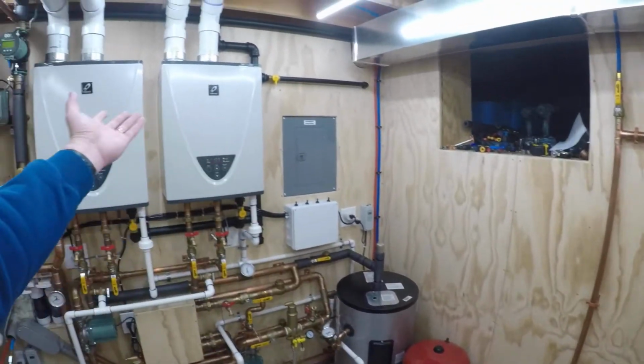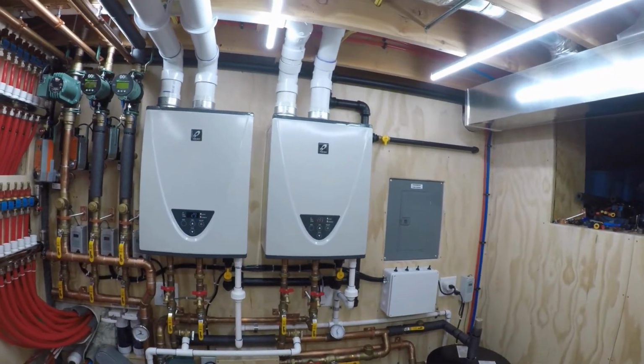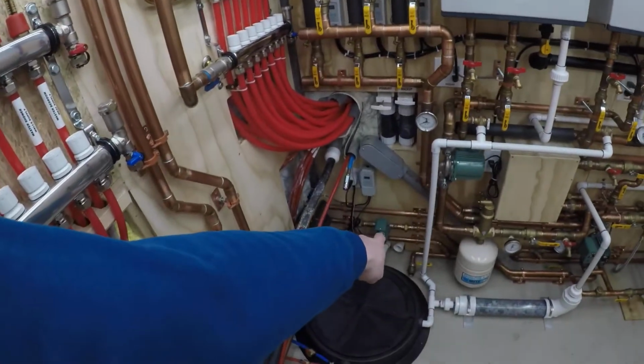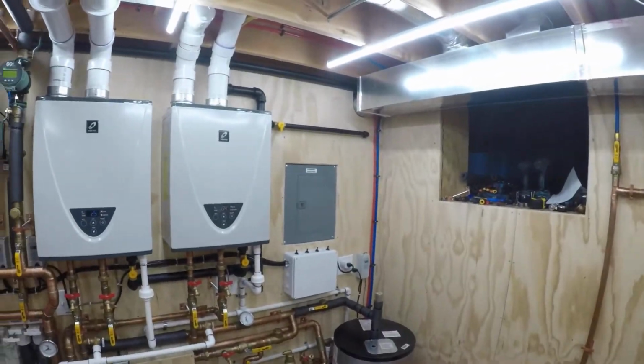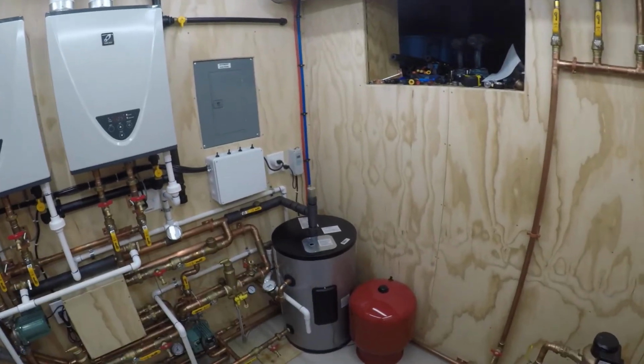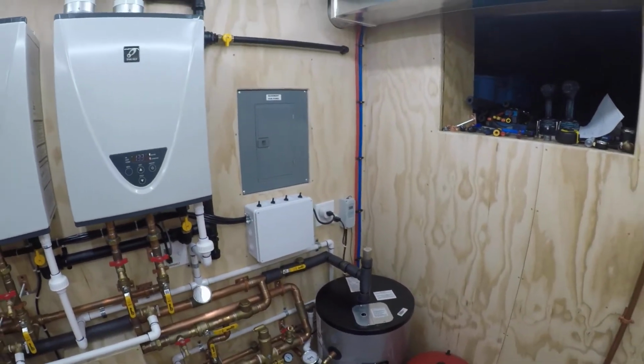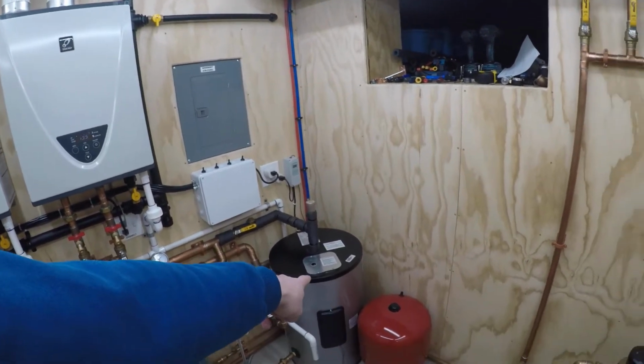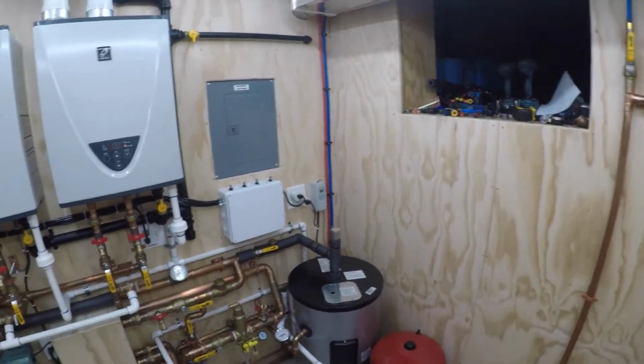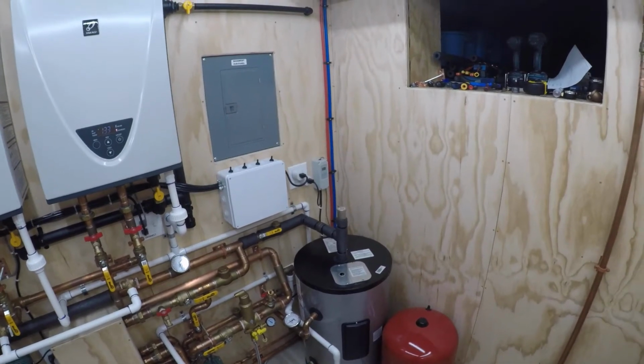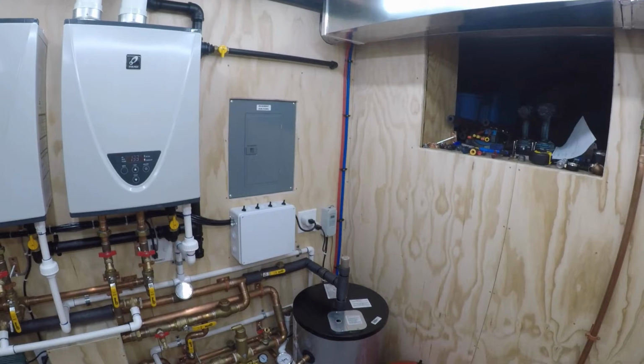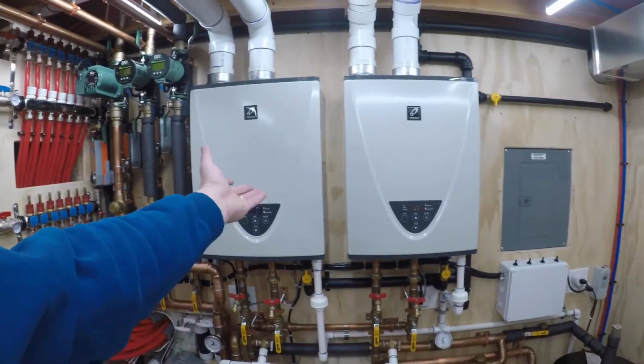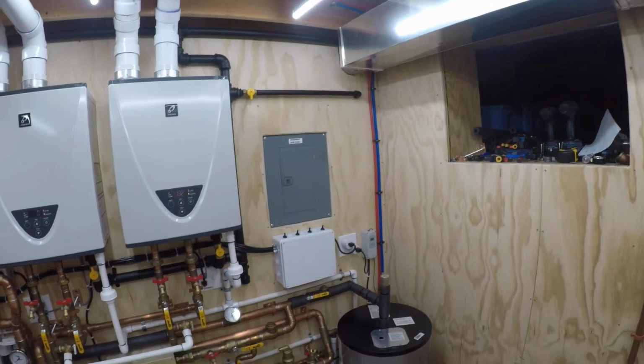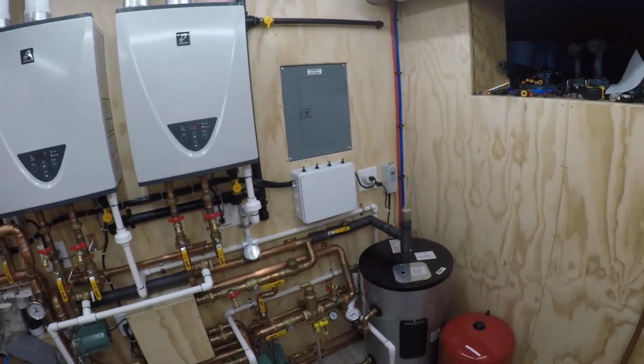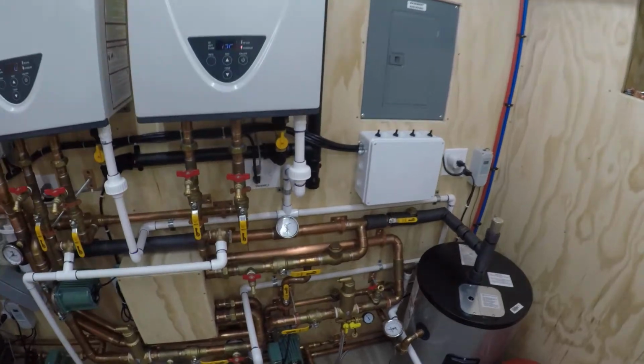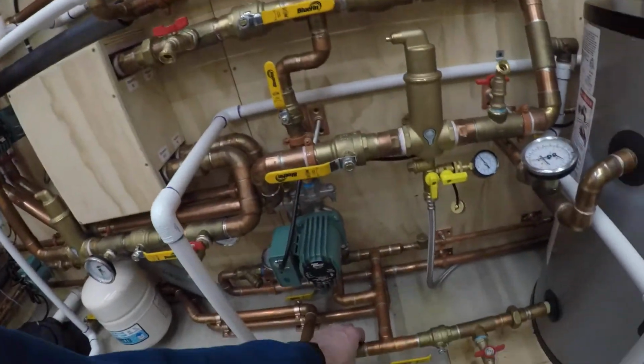This thing really only runs these heaters about once every hour and a half, and at night when I turn off that recirc pump, this setup will go 7 hours and it won't recirc the water in that tank, because it actually takes 7 hours for the water in that tank to drop from 131 to 125. It loses about a degree an hour. It's a very efficient little tank. So, you know, to burn at 45,000 BTUs for 3 minutes, it's nothing. It's very efficient even to do my domestic. So that's the hot water recirc here.